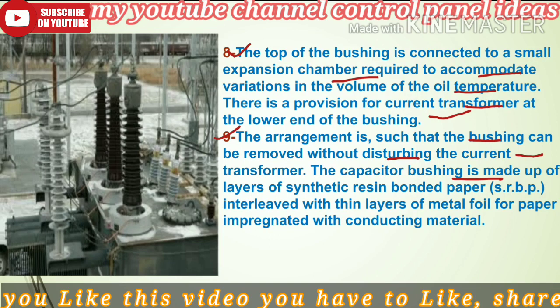synthetic resin bonded paper, SRBP, interleaved with thin layers of metal foil, or paper impregnated with conducting material. This is the bushing and this is the CT, current transformer.